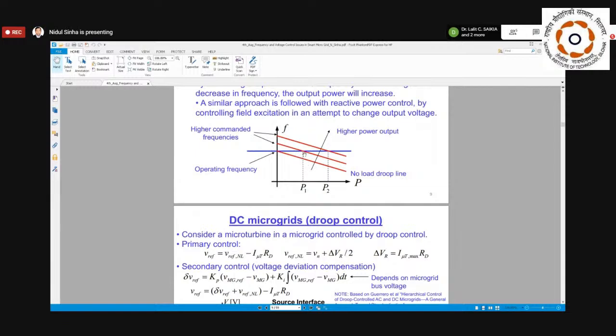So what we have to do is shift this characteristic upward or downward. That means the controlling action, other than this droop control, is the secondary control, which is also called supplementary control because it should be supplementary in nature.